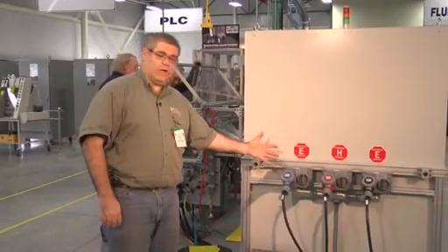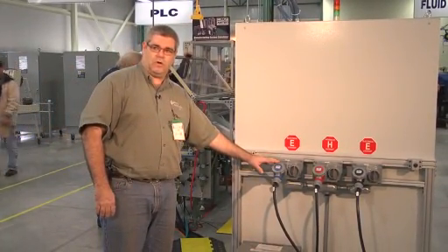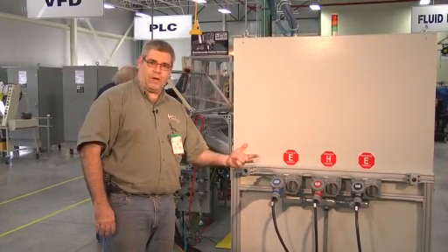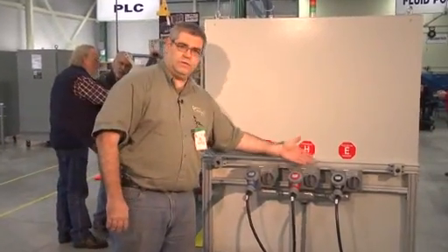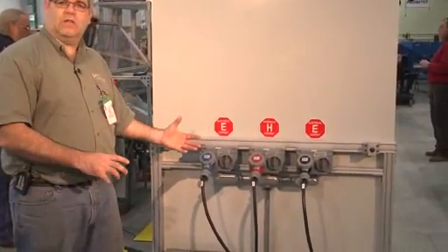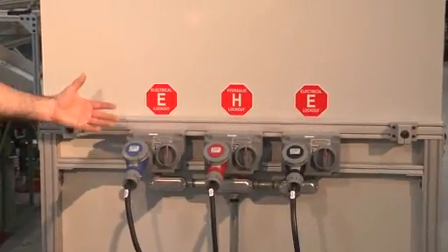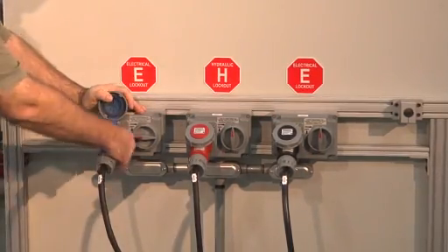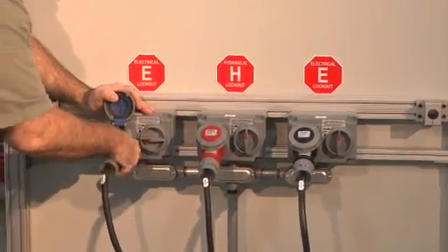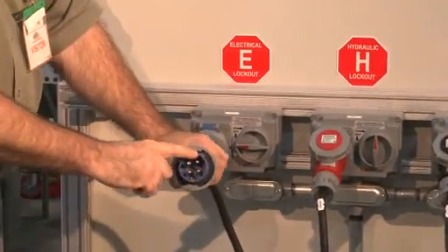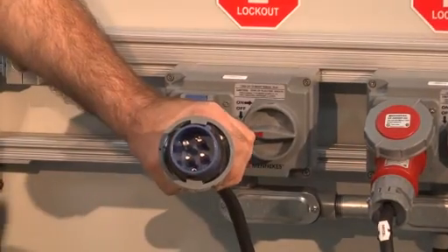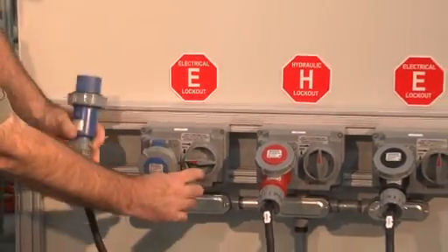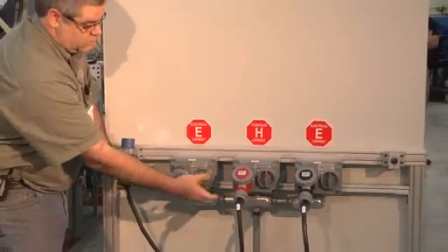Okay, and on the back of the machine here we have lockable disconnects that have quick connect plugs on them, and those plugs go out to the VFD motor, the hydraulic motor, and robot power. And if you look right here, you can see they're color coded as well as keyed so that you can't get the power sources wrong out into the field and destroy something. And they are lockable, so we can turn it off and put a padlock in here and lock it out, and you can also remove them. And you can see that they got keyway and different pin power. And with this removed, you can't turn the disconnect on, it will not work.